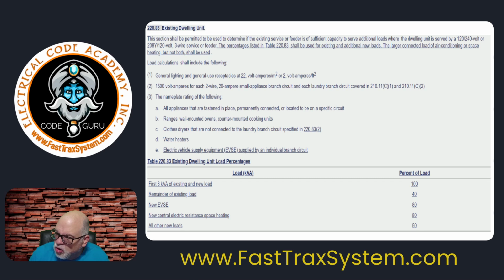If you're adding a new central electric resistance space heating, again, this is new. Remember, if it was existing, you're already adding it in the top part anyway. So if it's new, and that's why it's important you see the word new in there, new electric resistance space heating, you take it at 80%. So whatever its nameplate is, you're going to take it at 80%.